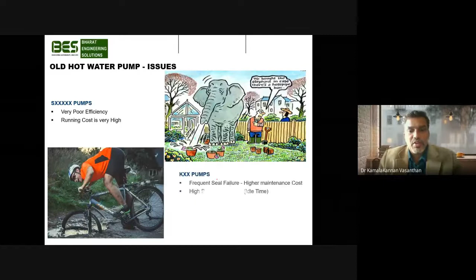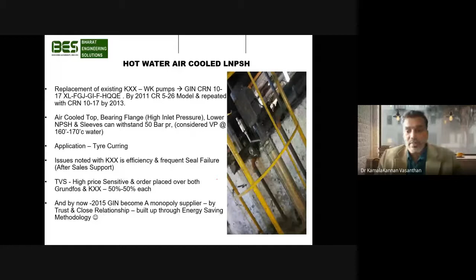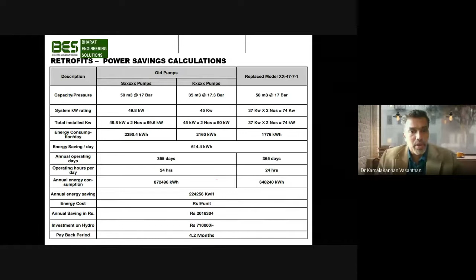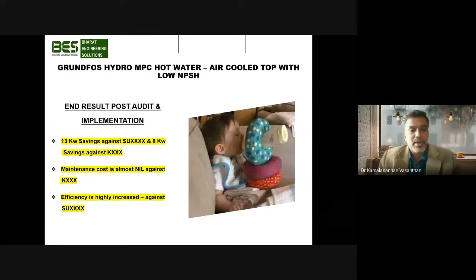And similar tire curing applications in a company called TVS Tires, where they had issues of very poor efficiency, high running cost, and frequent seal failures with regards to the particular pump. Every week or 10 days the seal had to be replaced, and those pumps were replaced with efficient pump selections against the site conditions, with a payback period of almost 4.2 months. 13 kilowatt savings with regards to the company and 8 kilowatt savings with the second company, and maintenance cost is almost nil.